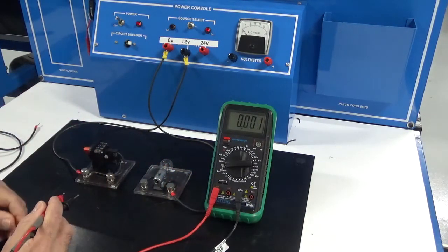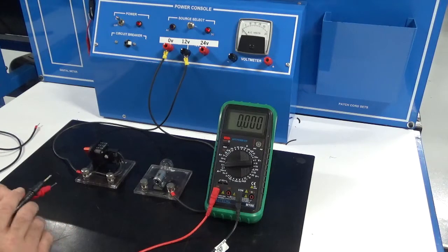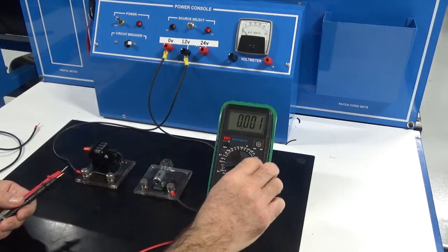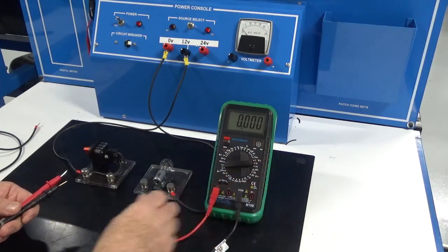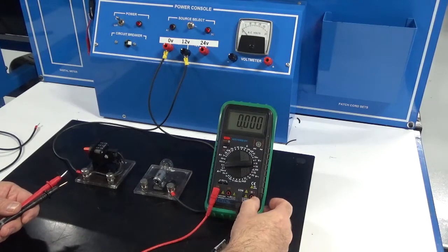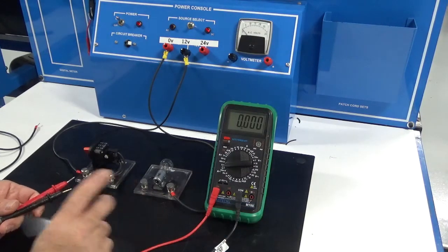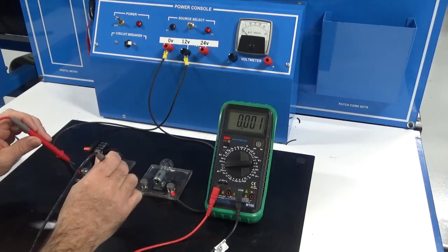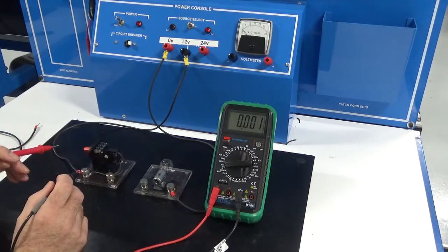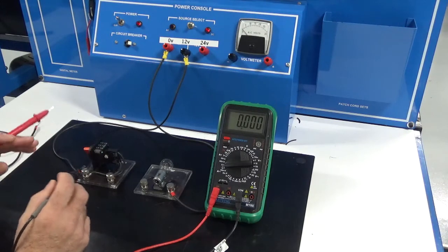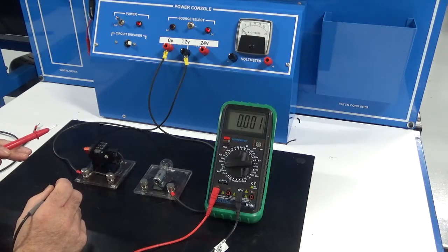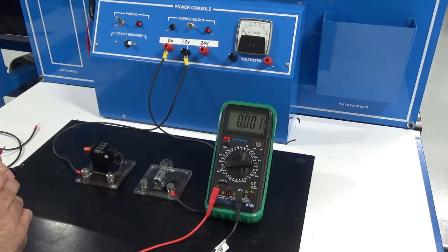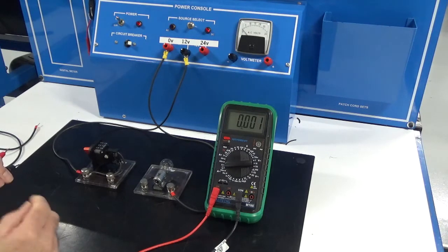So to review, to do a voltage read, we set the meter up for voltage, make sure we're in the correct AC or DC, have the probe in the correct port or the correct jack on the meter, and then when you take the read, you just basically touch across 2 points, and the meter will tell you the difference in potential between those 2 points. And again, it's not telling you if voltage is present, it's just telling you if there's a difference in potential between the 2 points you're testing.